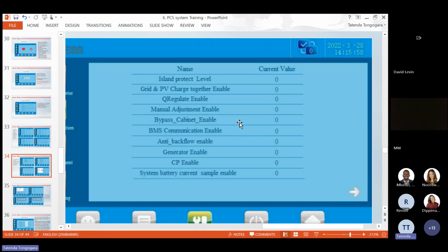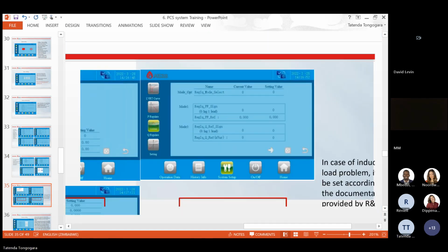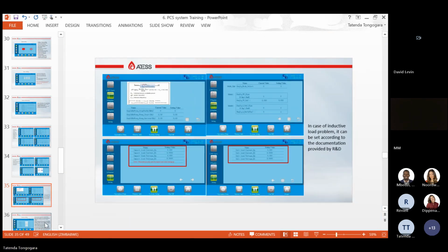So inside the bypass, we have grid input, generator input, and then we also have the PV input. On our settings, it's called CP. That's our PV input. I see in SA there are a lot of sites that have grid-tie systems only, and now clients want to put in a backup system. So you can take your PCS and put it in the same circuit with the grid-tie inverters. You connect the output of the PV inverters to the PV input inside the bypass. And then you have to enable CP here, enabling your PV input, so that the system will know that I have PV inverters connected to the system.